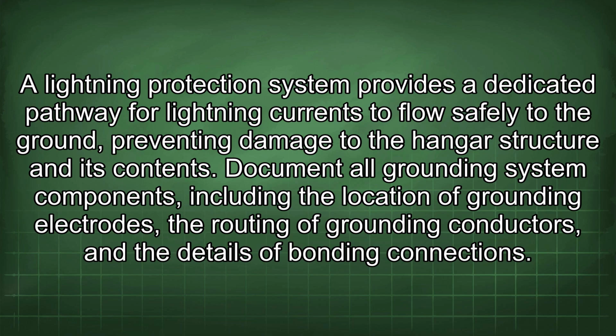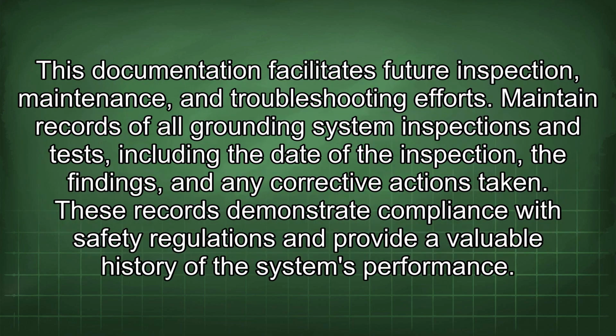Document all grounding system components, including the location of grounding electrodes, the routing of grounding conductors, and the details of bonding connections. This documentation facilitates future inspection, maintenance, and troubleshooting efforts. Maintain records of all grounding system inspections and tests, including the date of the inspection, the findings, and any corrective actions taken. These records demonstrate compliance with safety regulations and provide a valuable history of the system's performance.